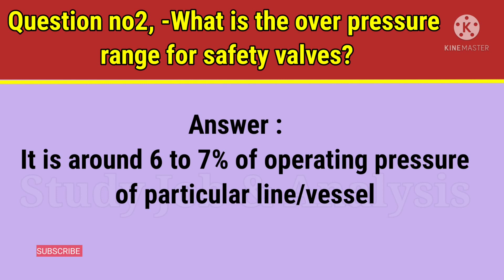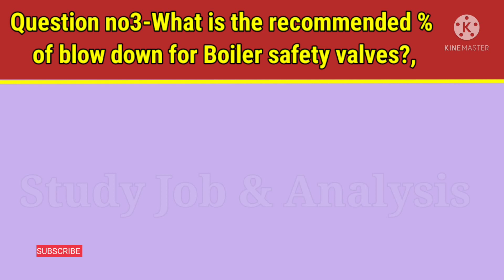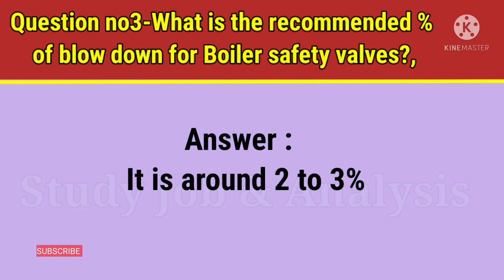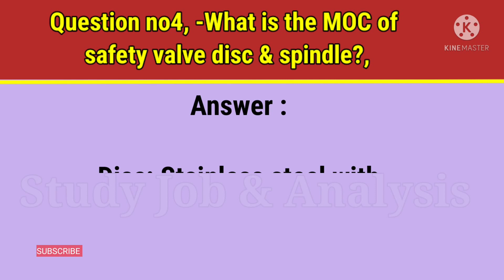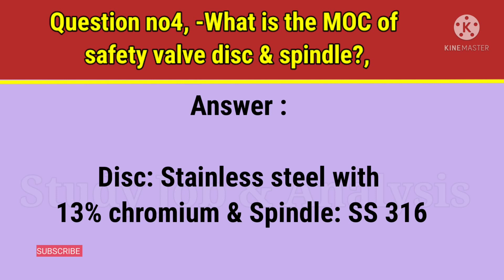Question number 3: What is the recommended percent of blowdown for boiler safety valves? Answer: It is around 2-3%. Question number 4: What is the MOC of safety valve disc and spindle? Answer: Disc — stainless steel with 13% chromium; and spindle — SS-316.